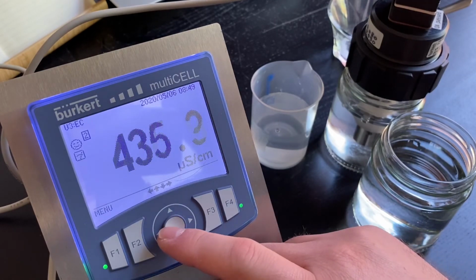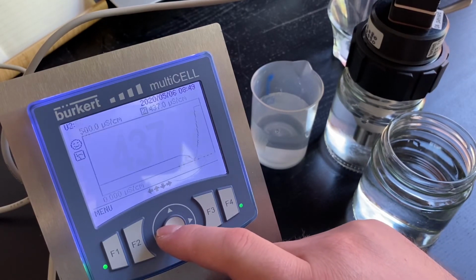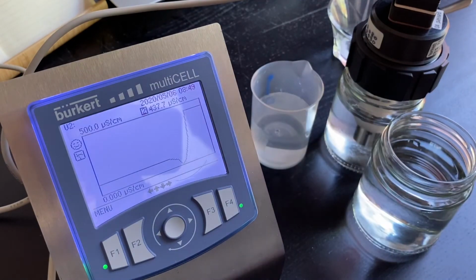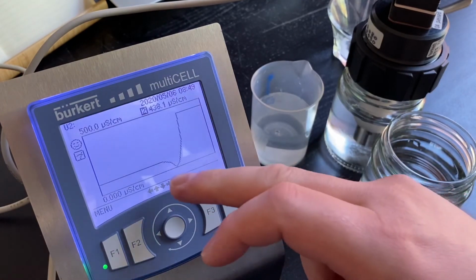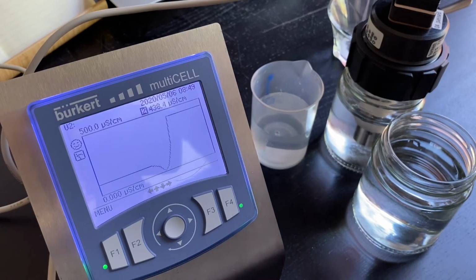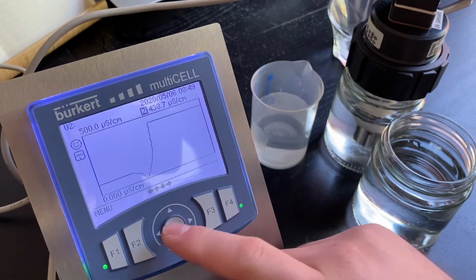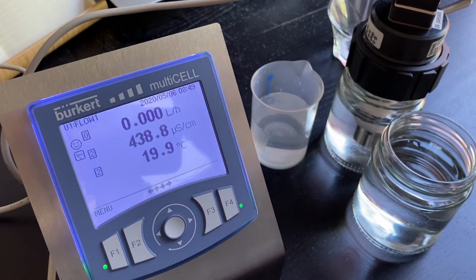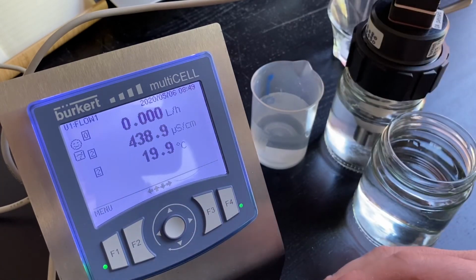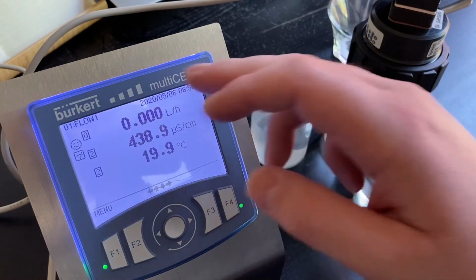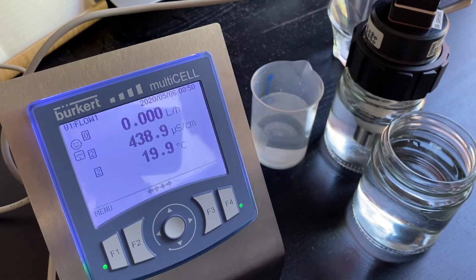If I go back one position, you can see now we've got a graphical display. The graph is a range from 0 to 500 microsiemens. We can increase that, we can decrease that as per the normal operating range. If I go back another position, you can now see that we've got multi-layer. You can see temperature for the sensor as well as the conductivity. And we've also got liters per hour at the top here. That's because we've got a flow sensor that's also connected to the Multicell. So we can see 438 microsiemens there.